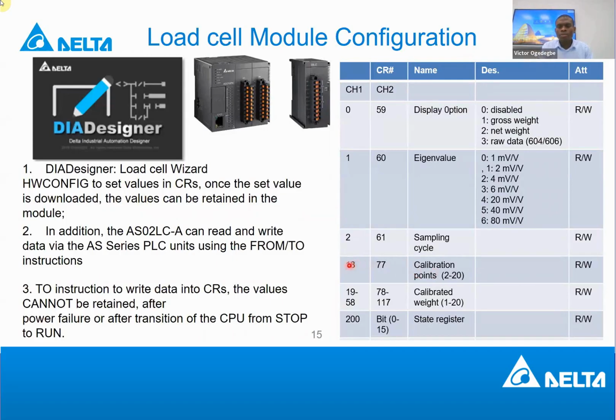And just as you can write to these registers with this API, in the load cell wizard it's also possible to access this function. But this is more robust, because what this can access, the load cell does not have access to. So the load cell wizard has access to very important registers. With the load cell wizard, you can configure the eigenvalue, the sampling time, and some very sensitive parameters. But other parameters, you don't have access to from the load cell wizard.